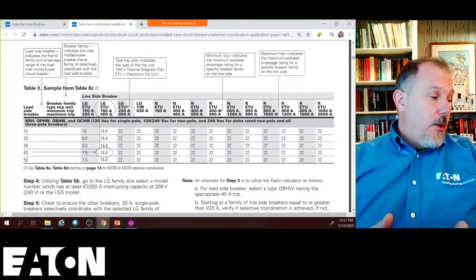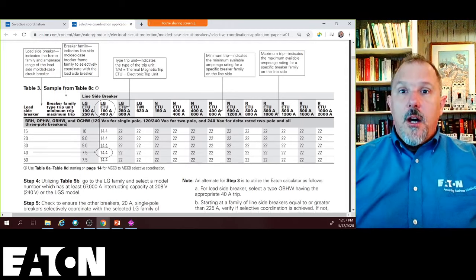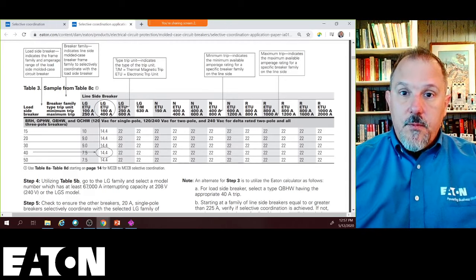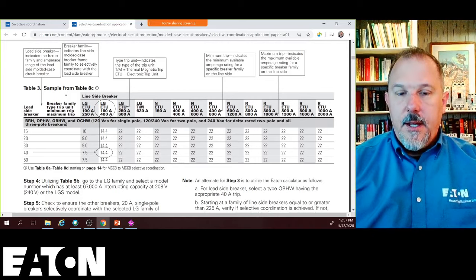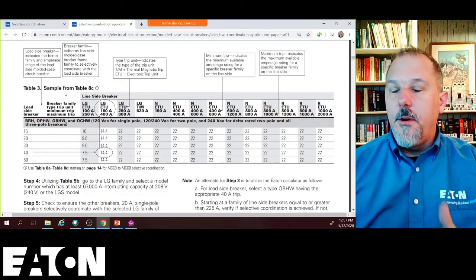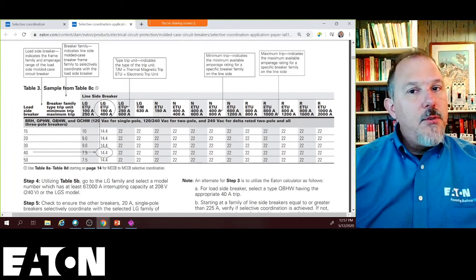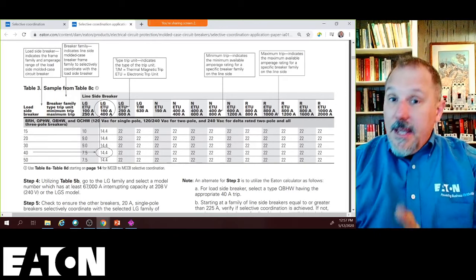You can do IEEE 242. It tells us that the most common fault in a power distribution system is your arcing ground fault current, which we calculate in IEEE 1584. So you could take the arcing current and say, look, I'm going to coordinate to the most common fault in a power distribution system.